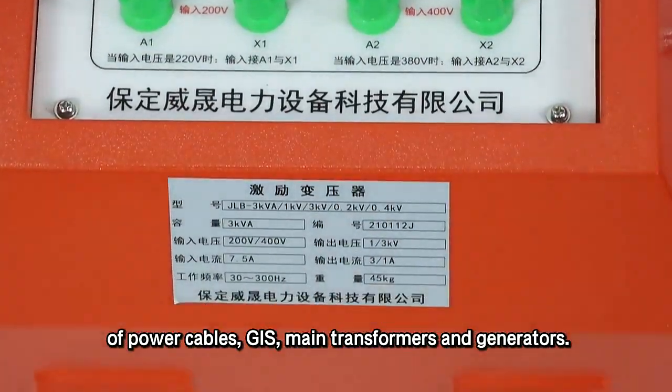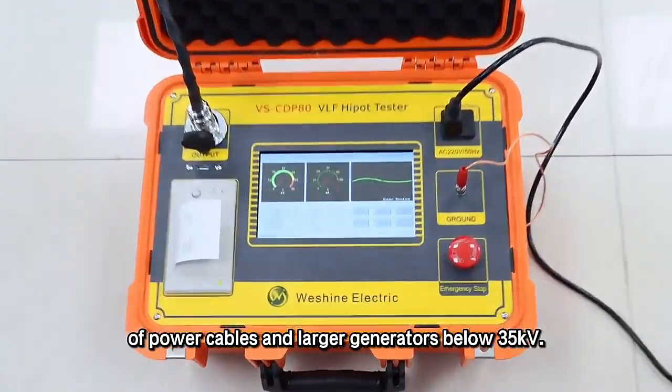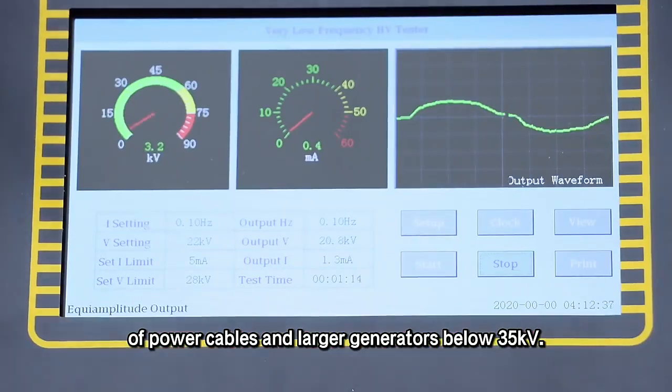It is also suitable for main transformers and generators. The VLF hipot tester is suitable for AC testing of power cables and larger generators below 35 kilovolts.